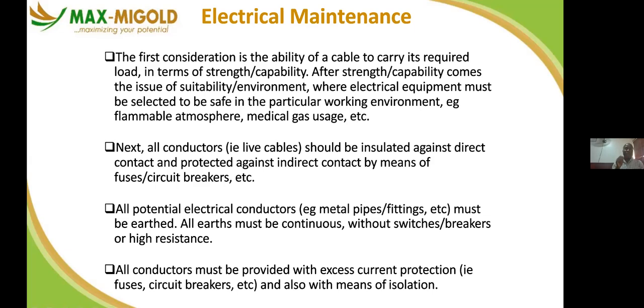They call it all potential electrical conductor. In most cases, like in the old days, there used to be plumbing pipes that are galvanized. So if you are in such a situation, they said they are potential electrical conductors. So they can have contact with leakage current and they become live. What you need to do is to ensure that they are earthed, they are protected, so that the lives of your personnel are safe, even at your home is safe.